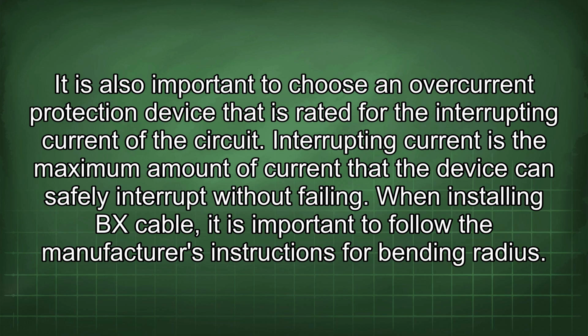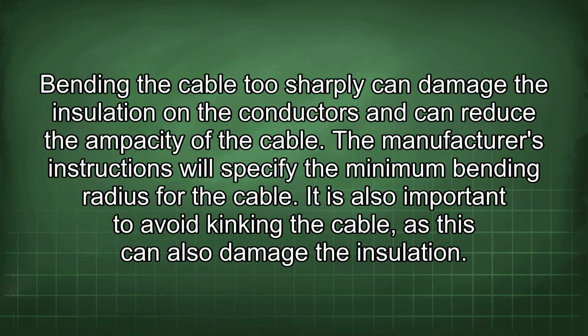When installing BX cable, it is important to follow the manufacturer's instructions for bending radius. Bending the cable too sharply can damage the insulation on the conductors and can reduce the ampacity of the cable. The manufacturer's instructions will specify the minimum bending radius for the cable. It is also important to avoid kinking the cable, as this can also damage the insulation.